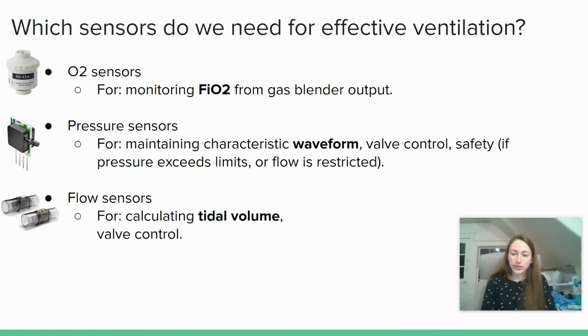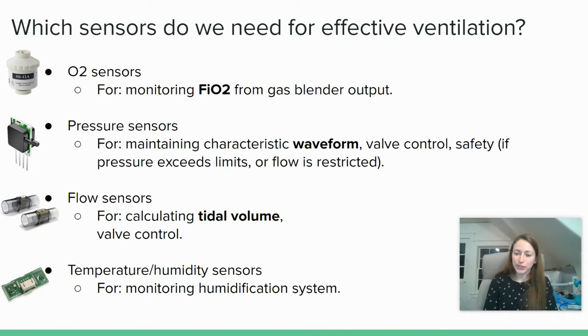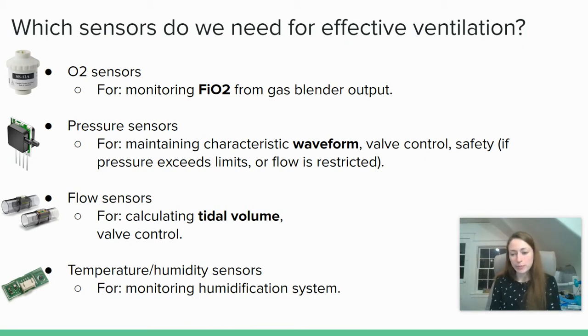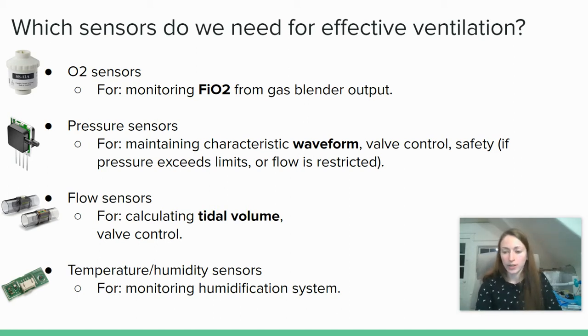For similar reasons, we're also going to need flow sensors. Beyond performing part of the control, these are essential for calculating tidal volume, which we want to monitor so we're not over-inflating the patient's lungs. Finally, we're going to need temperature and humidity sensors — you may get away with just a temperature sensor depending on where you're operating — essentially for monitoring your heated humidification system. For example, if working with a heated humidifier, you want to ensure you're not burning the patient's lungs with overheated air in the event of mechanical failure. These are for display and alarm monitoring, not device control.